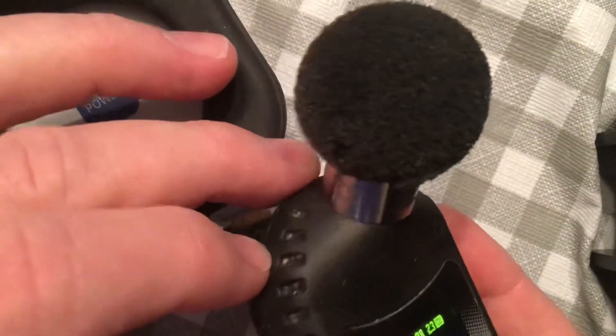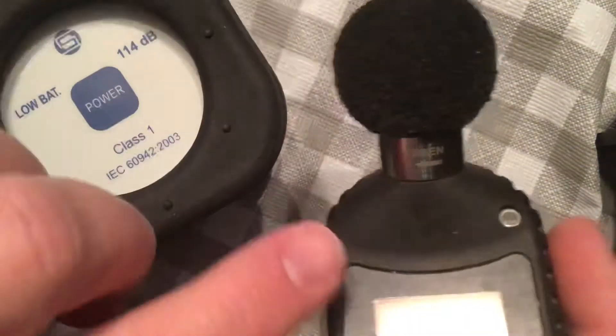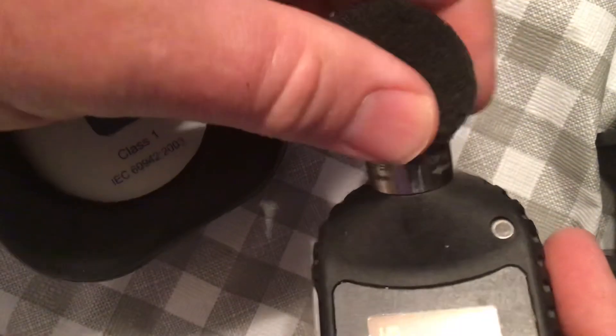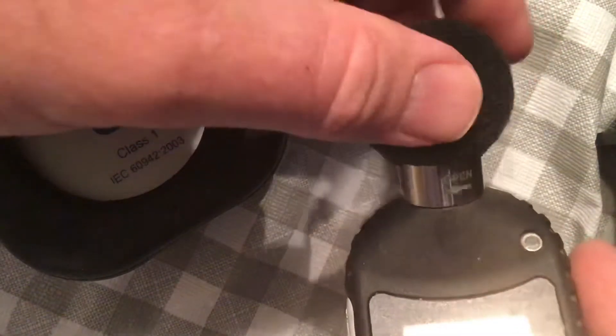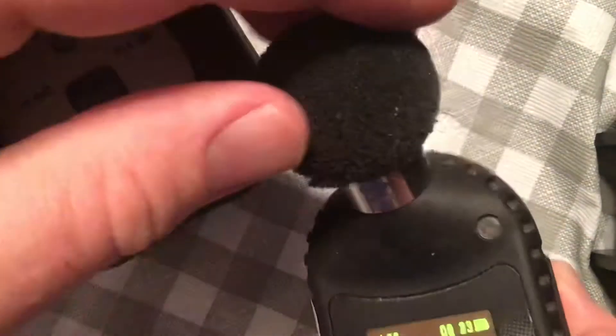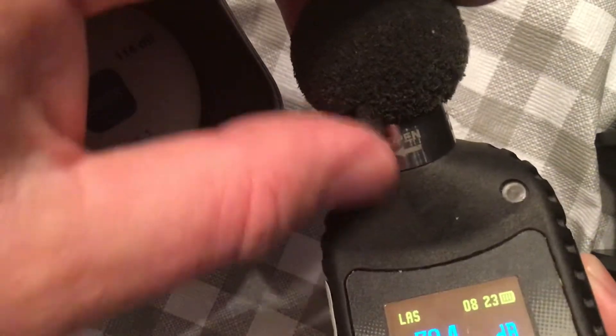With the intrinsically safe version, it's actually when you're unscrewing this part of it — it's a reverse thread. Some customers will get it and try to unscrew it the wrong way, so we need to make sure we pay attention to the way the arrow indicates to unscrew this.